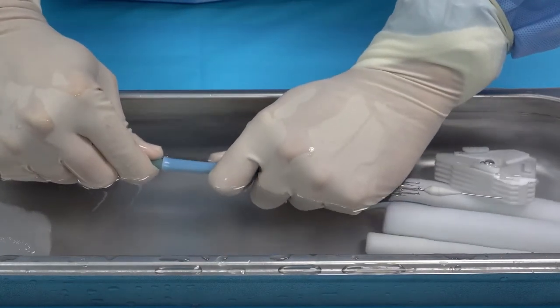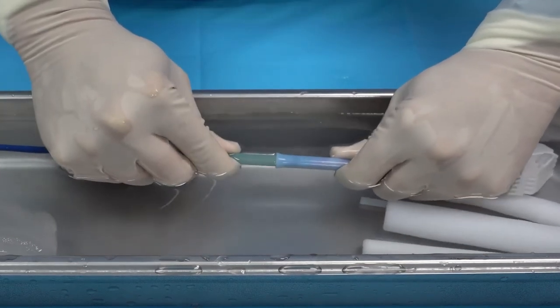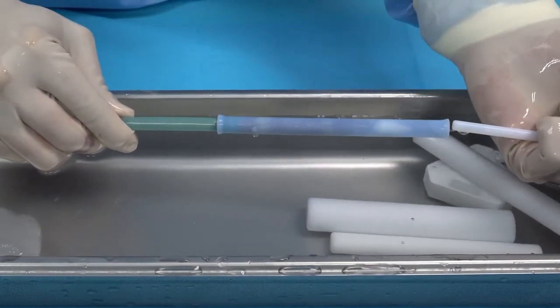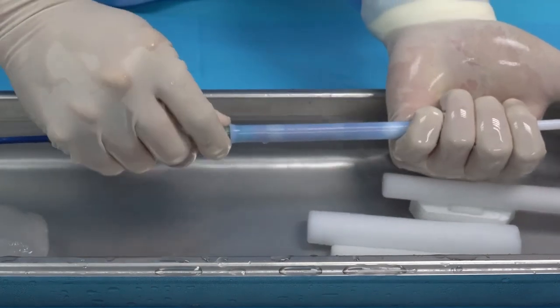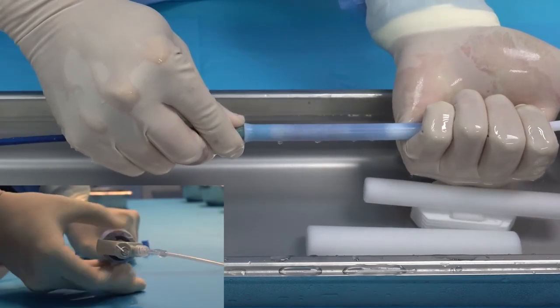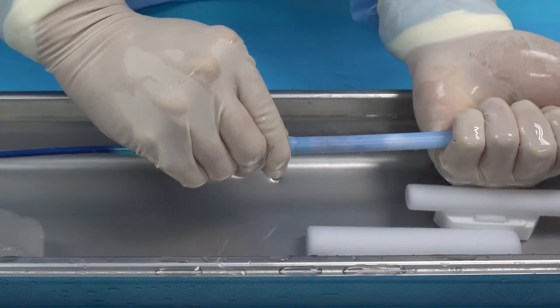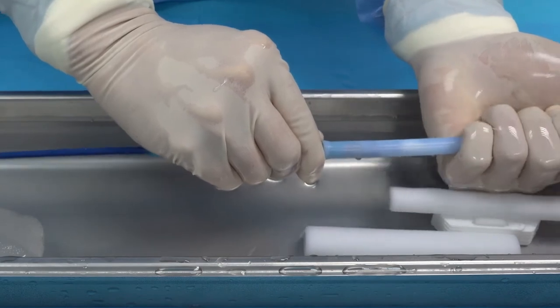Hold the loading tube with the left hand and pull back until the loading tube reaches the golden opaque ring. Insert the support tube from the distal end of the loading tube and against the head or carrot of the delivery system. Hold the support tube with the left thumb and gently slide to advance the capsule tube with the right hand until the head or carrot.